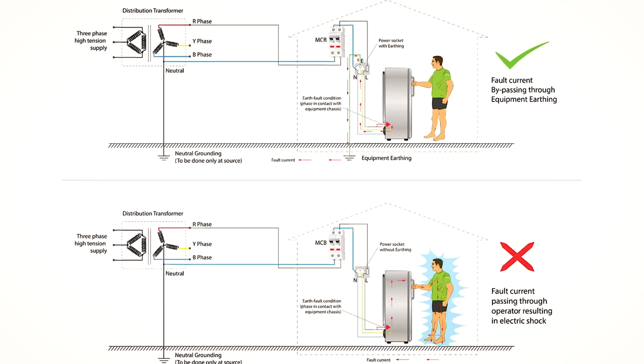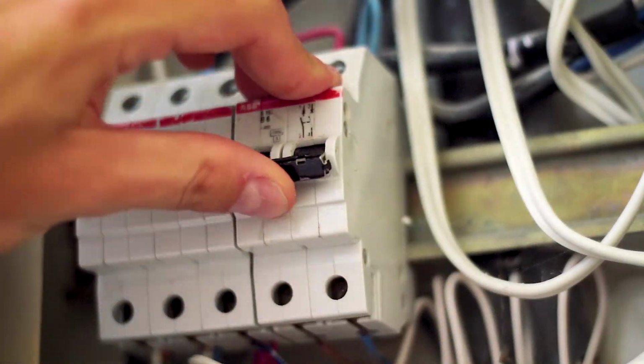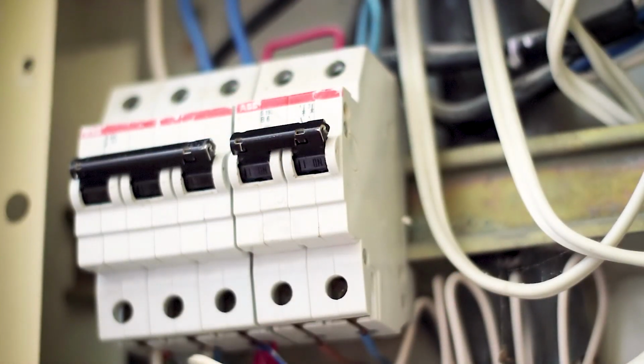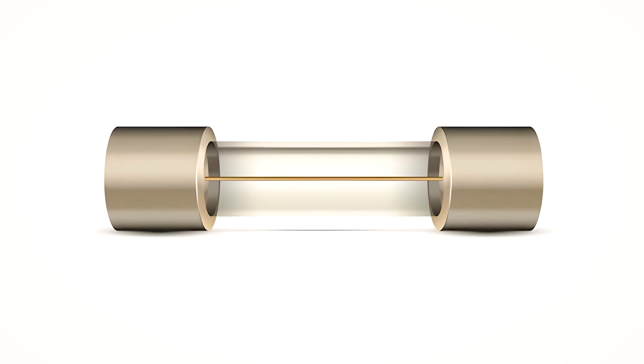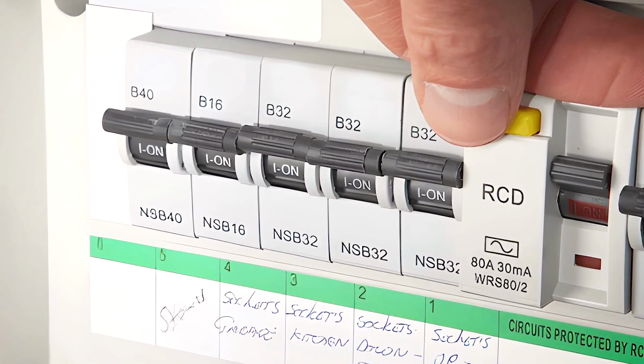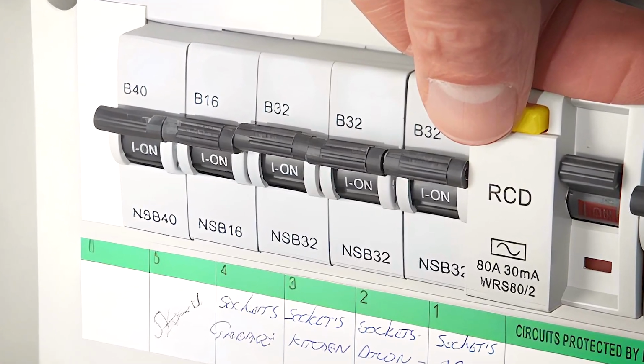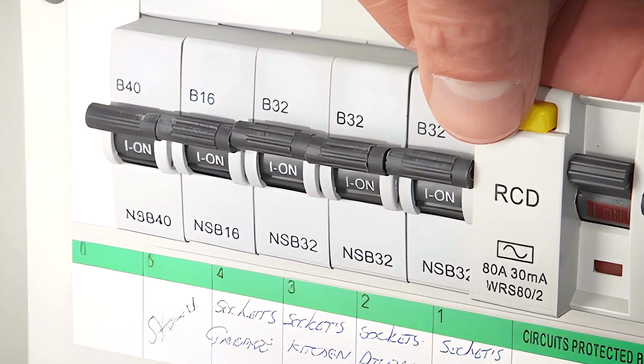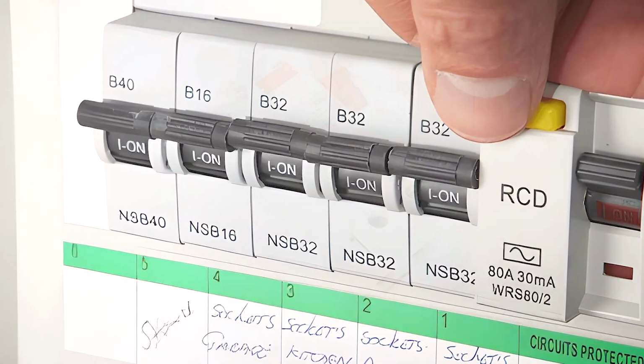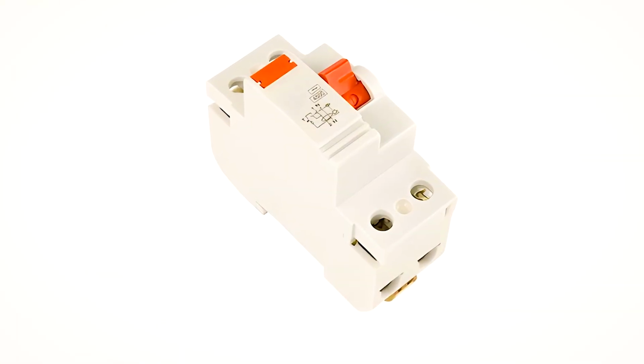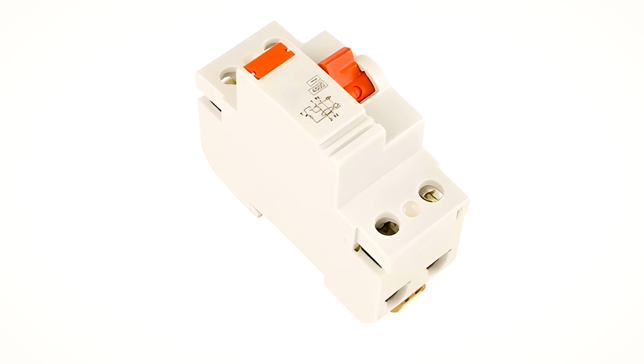Grounding prevents this by ensuring that fault current flows rapidly into the earth instead of through people or sensitive equipment. This rapid flow of current causes protective devices like circuit breakers, fuses, and residual current devices, RCDs, to detect abnormal conditions and disconnect the supply within milliseconds, drastically reducing the duration and severity of exposure.